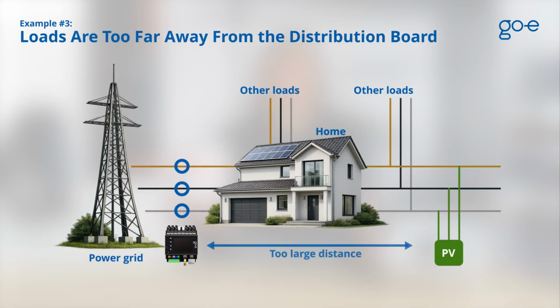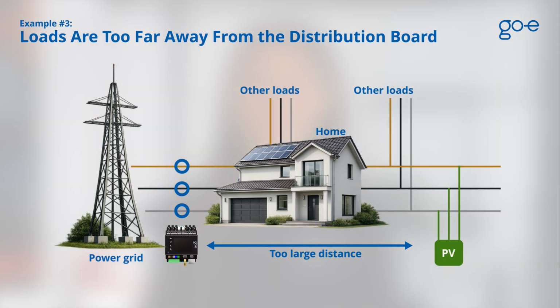If your solar inverter is installed too far away from the distribution board with the GoE controller so you can't measure it directly, that's not a problem. For PV surplus charging, direct measurement of solar production isn't required, as mentioned earlier. However, if you'd still like to monitor your solar production, you can buy a second GoE controller and connect it to the first one via your home network.